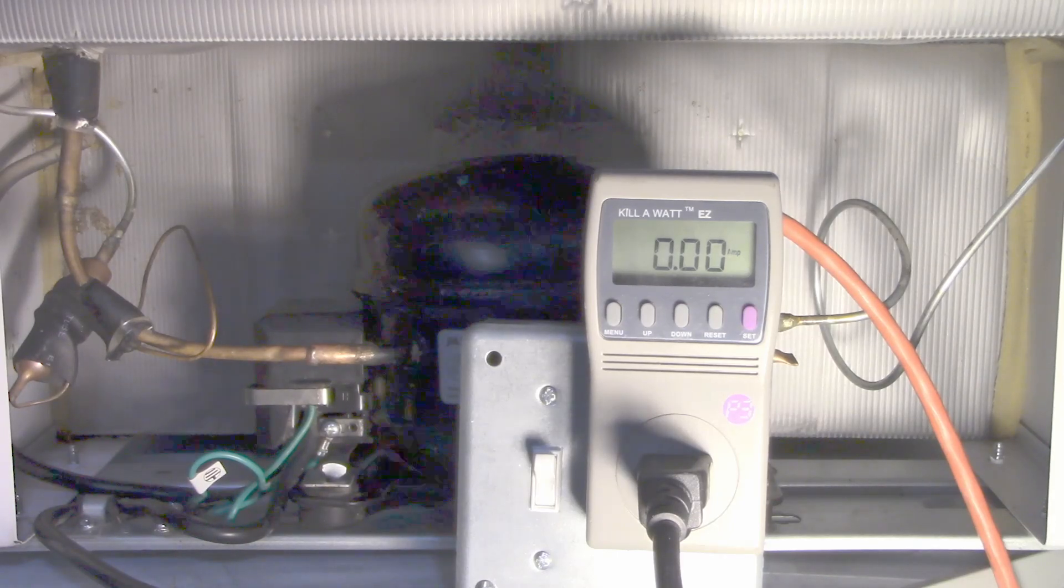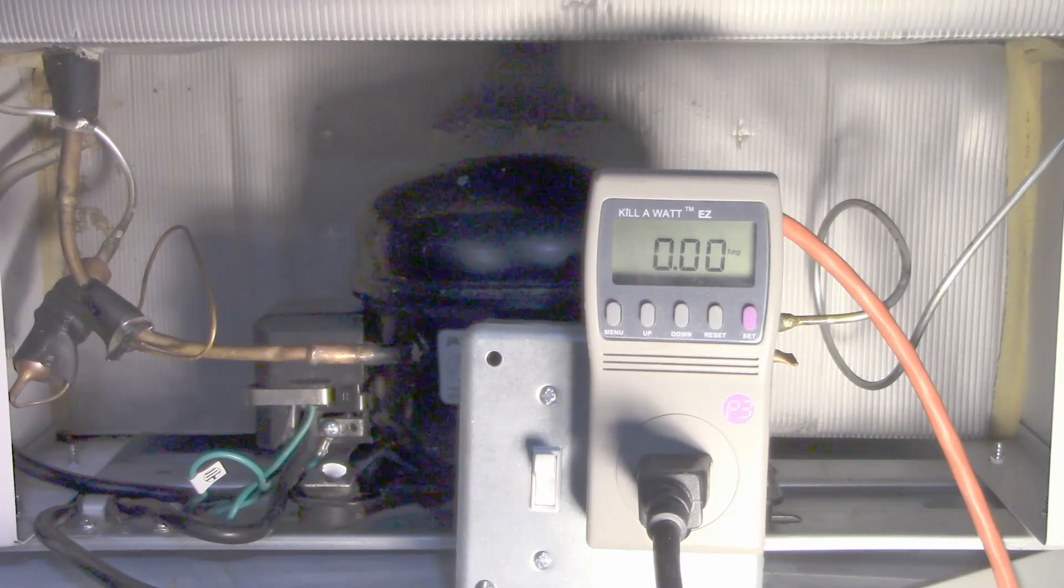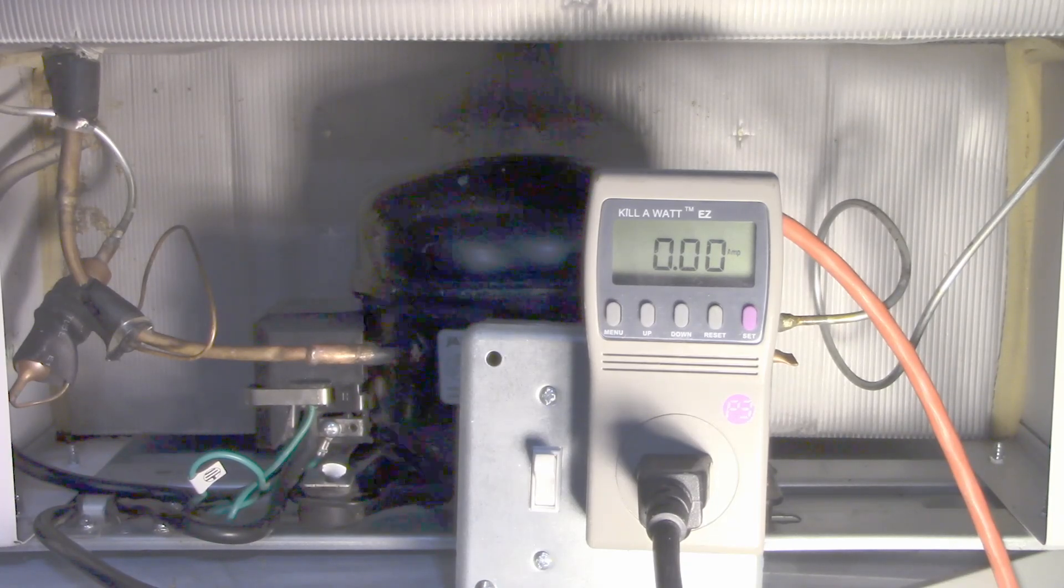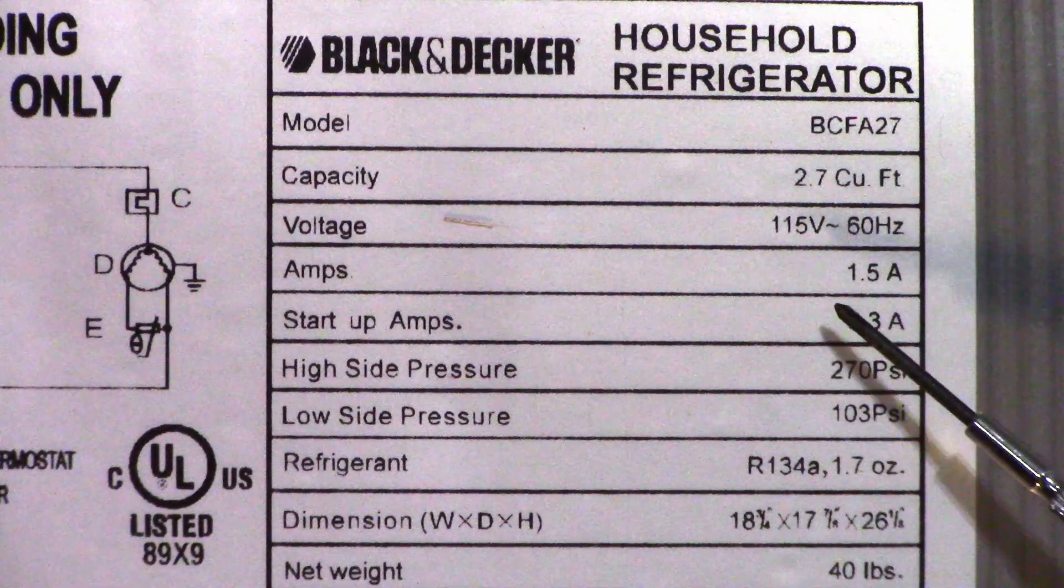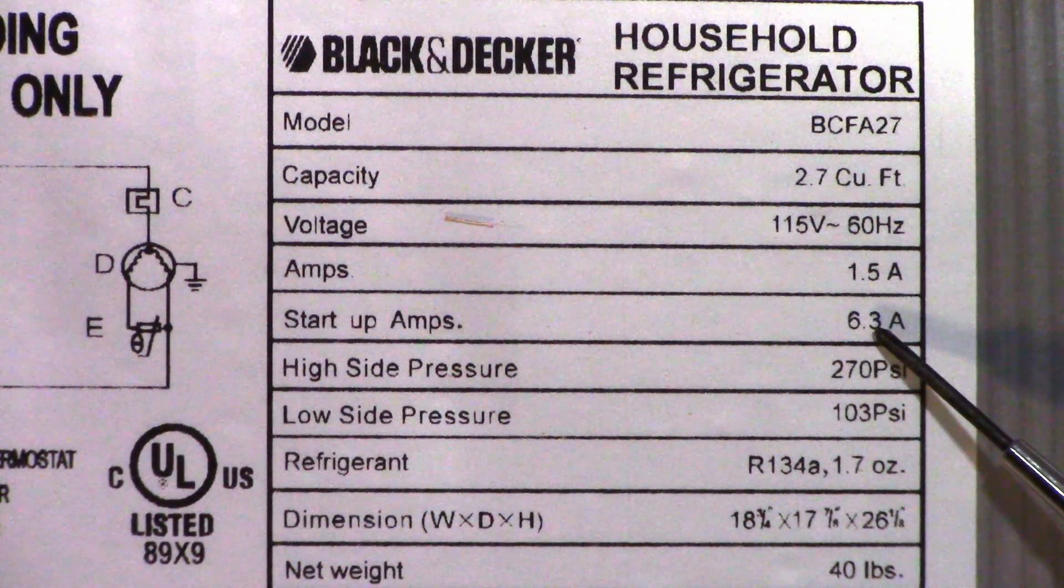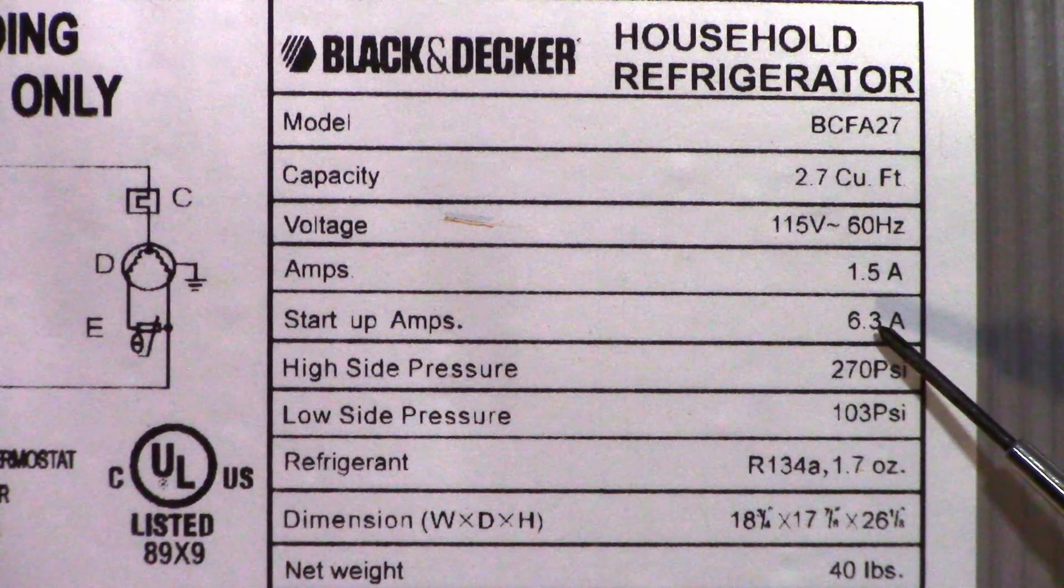So the compressor is definitely not starting. I'm hoping it's just that start thermistor, and I can devise a circuit to give it a little bit of juice for a split second to get this thing started. Here's the specs, startup amps 6.3, we were getting pretty close at over 5 amps. Normal running amps should be 1.5.